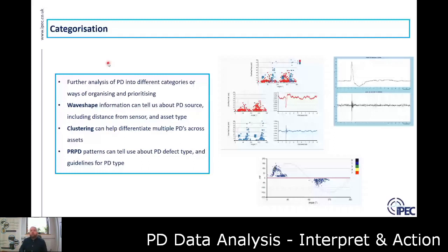We have PD being detected by our monitoring system, by different sensors. We may also be detecting multiple PD activity — PD from multiple assets, cable or switchgear. We want to do further analysis to find out where our PD may be.